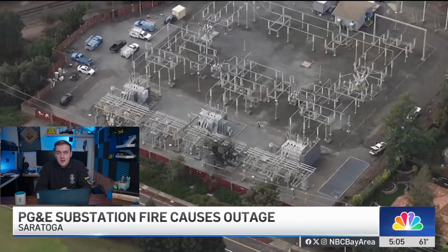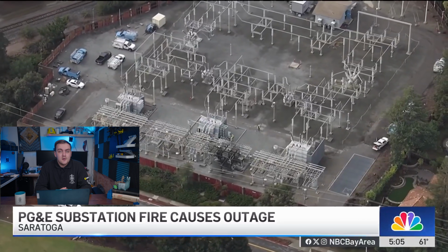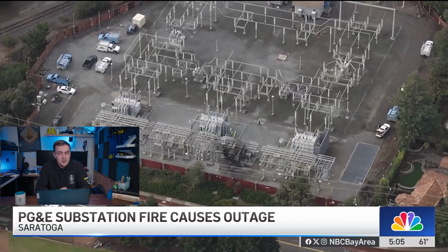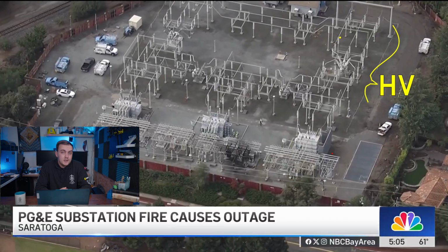Looking at this nice wide shot here at the start, we get to see the higher voltage equipment at the top of the screen, because the gaps between the bus bars which carry the power are much larger, which is for the higher voltage, because higher voltages can more easily bridge a gap by arcing. So we need to separate them. In comparison, at the bottom of the screen I can tell this is a much lower voltage because all of the bus bars are close together, and more on that in a second.